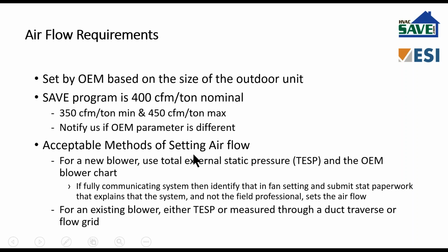Okay, acceptable methods of setting airflow. For a new blower, use the total measured external static pressure and the OEM blower charts. This is a fresh blower. The OEM gives us the data. It's typically in the install manuals. It's right there. Let's use it, okay?